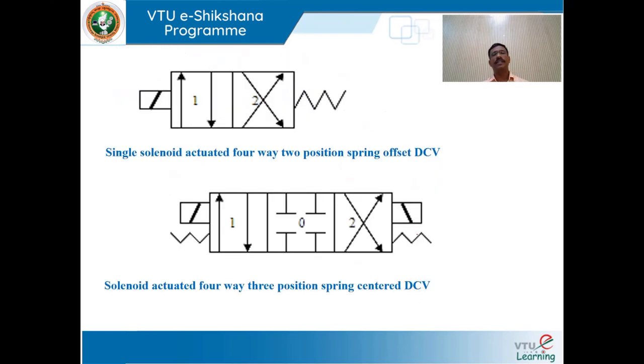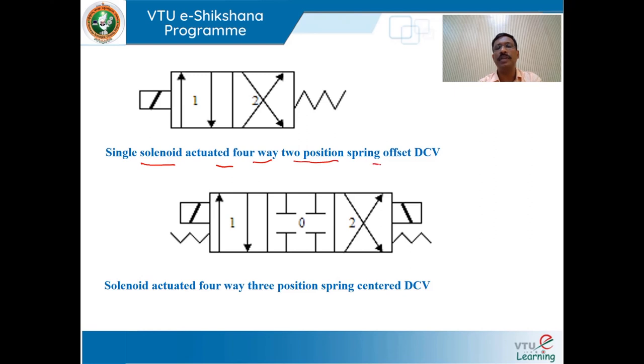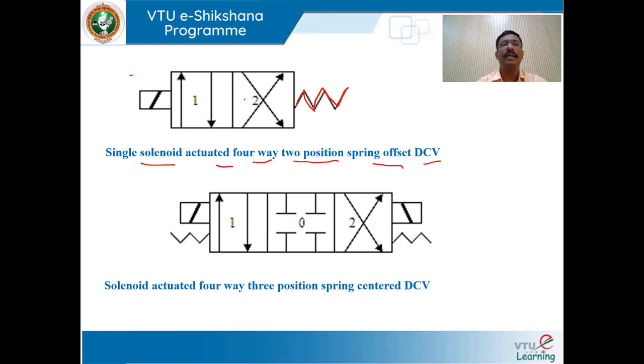We shall draw a symbol for a single solenoid actuated four-way two-position spring-offset directional control valve. Two-position: position 1 and 2 shown by two squares. A spring is provided on one side of the valve and a single solenoid on the other, where current flows to the coil energizing it to actuate the valve.